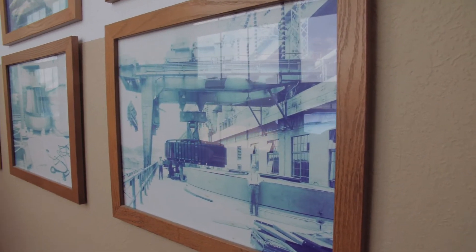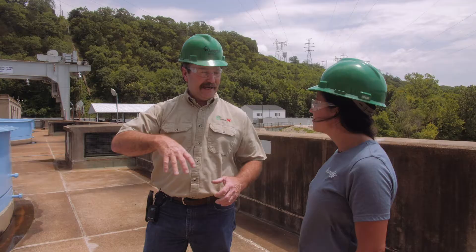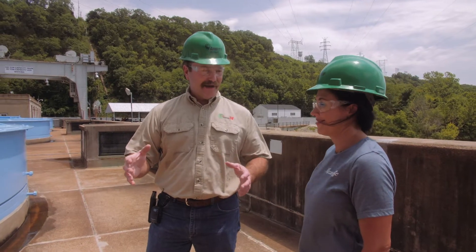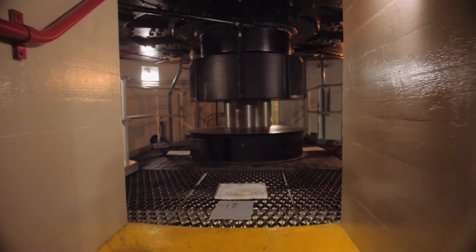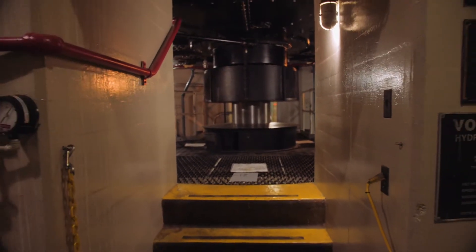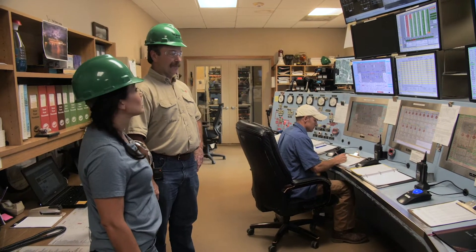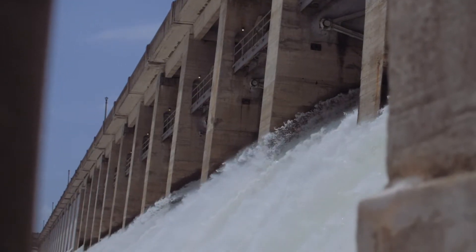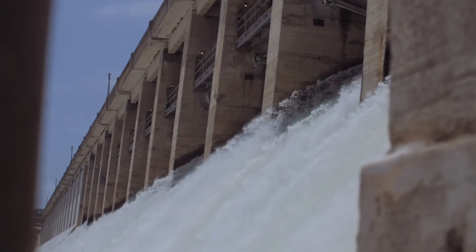The machinery is very well balanced — even though you feel a little vibration, there's about 250 tons rotating that's very finely balanced, so you don't get a lot of big vibration, just a little bit in the concrete. We operate three different power stations from this control room, all our hydropower plants. On the Mississippi River we were around 250,000 cubic feet per second of water flow, and the main generators can produce about 240 megawatts.